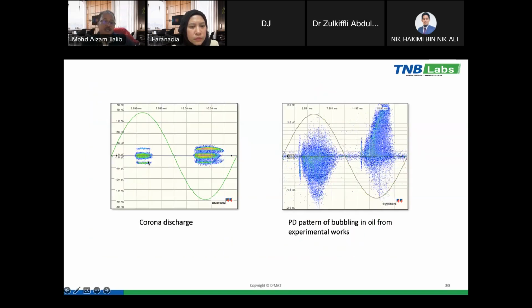And then this is an example when we have a corona discharge. Corona discharge normally occurs at 90 degrees, and the pattern is flat. So this is the corona, and this is the PD pattern. When we have bubbling in oil, it will give a straight vertical line in the PD pattern. So through these PD patterns, we are able to distinguish or differentiate the different faults in the insulation.